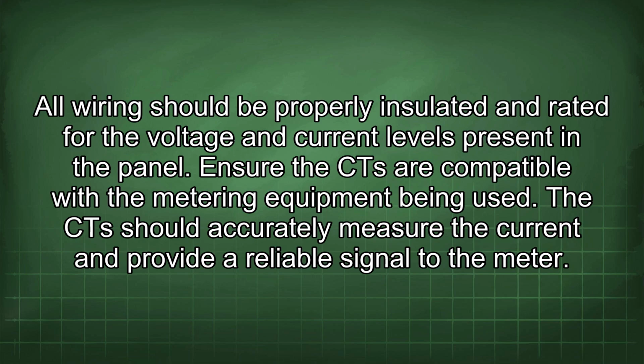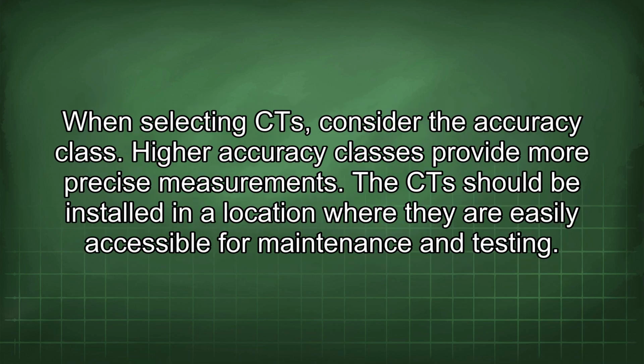All wiring should be properly insulated and rated for the voltage and current levels present in the panel. Ensure the CT are compatible with the metering equipment being used. The CT should accurately measure the current and provide a reliable signal to the meter. When selecting CT, consider the accuracy class. Higher accuracy classes provide more precise measurements.